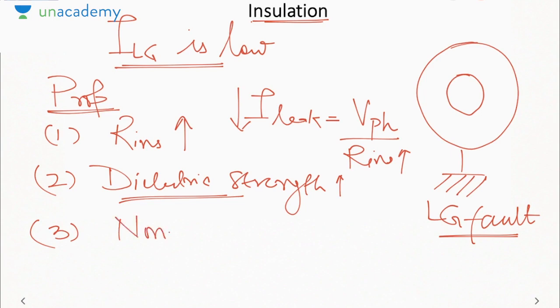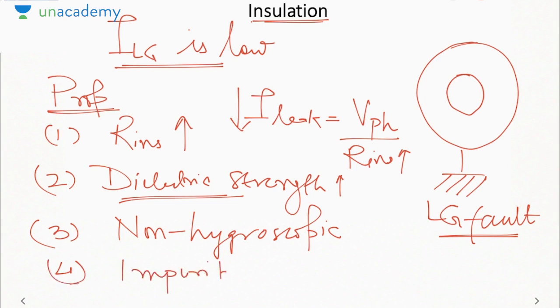Next is non-hygroscopic. Non-hygroscopic implies that the material should not retain water. Why should it not retain moisture or water? Because moisture will make it more conducting, and if it becomes conducting, then its insulation resistance will go down. That is why the material should not retain any moisture, that is, it is non-hygroscopic. Next is impurity free. As you might know from semiconductor theory, adding doping or impurities makes a material more conductive. That is why it should be highly pure, or less impure, so that its insulation resistance is high.